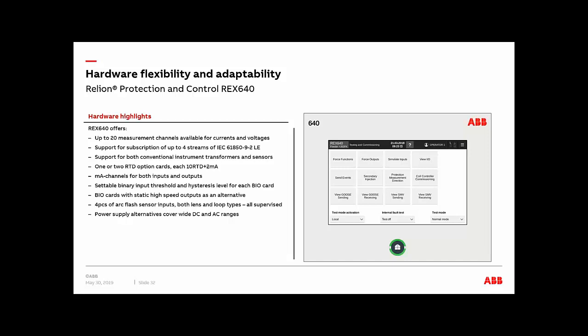You got threshold settable outputs. The BIO cards have the option for having high-speed outputs. If you have an application that requires high-speed tripping, you can have this option loaded on the relay as well. And you got 4 pieces of arc flash sensor inputs, which could be either lens sensors or loop types, all supervised type of sensors. This is new on this relay. Previously, some of the Relion series with sensor option were just point sensors. On this relay, you do have the option of having a loop type of fiber connected to the relay. And as far as power supply, you do have the option for AC or DC.